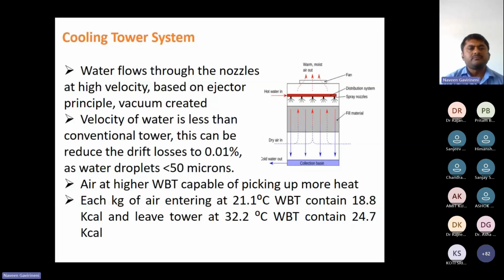This cooling tower system is for the cooling of the water. Generally, we supply this water to the condenser. The condenser performance depends directly on the cooling tower system only. There are three terminologies: wet bulb, dry bulb, and relative humidity. You just see, velocity of water is less than conventional. This can reduce drift losses to 0.01%. That means velocity also plays a vital role. Air at a higher wet bulb temperature is capable of picking up more heat.